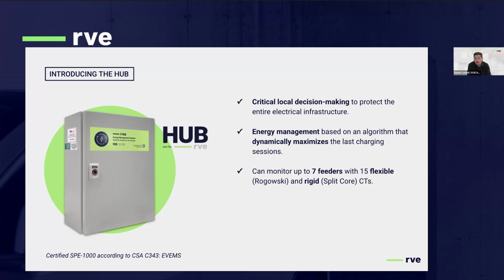The Hub enables monitoring up to 7 feeders or 15 CTs, with flexible Rogowski CTs or split-core CTs. It can control up to 120 DCC Plus units and up to 30 SMP Plus units, which we'll see a little later in the presentation, via a BACnet connection.